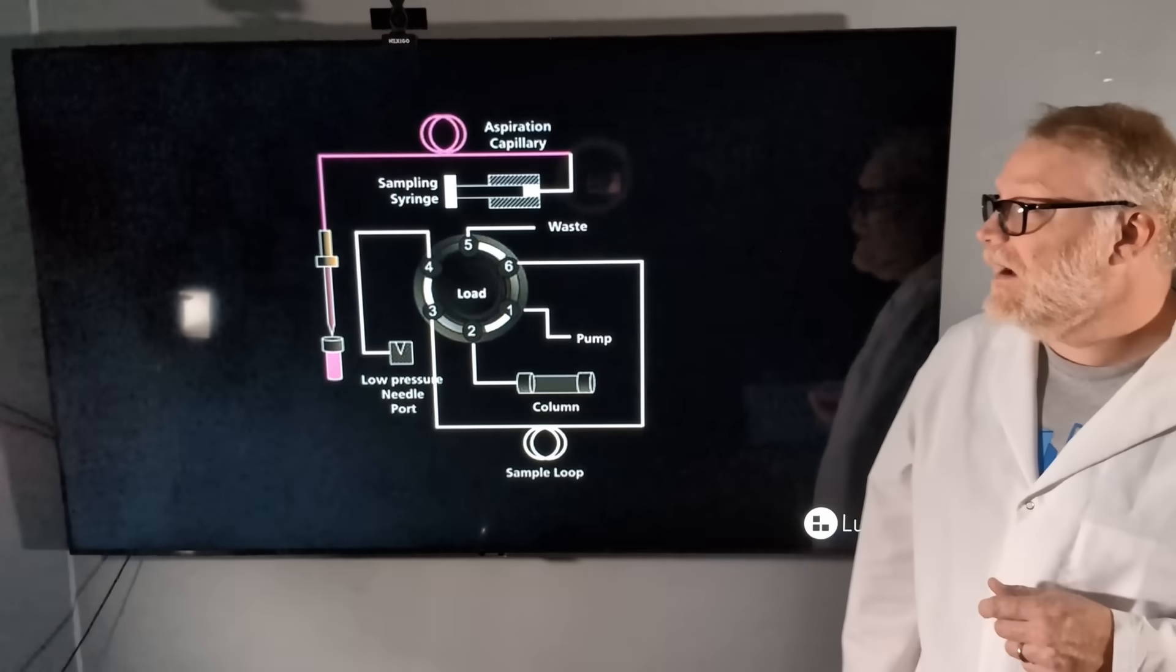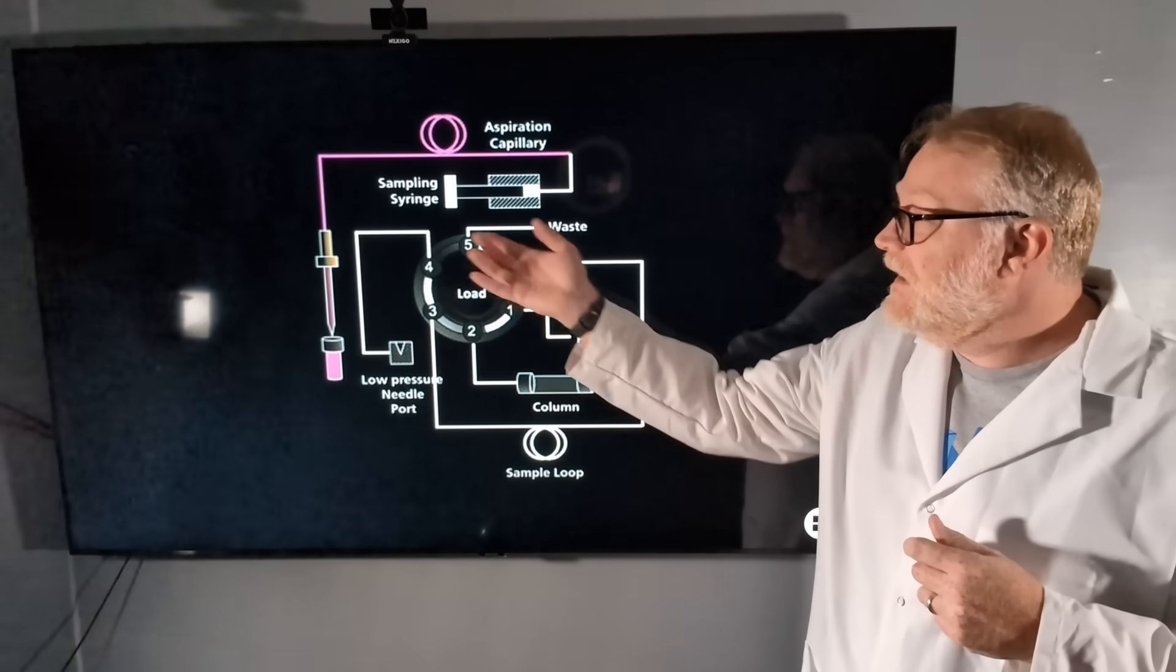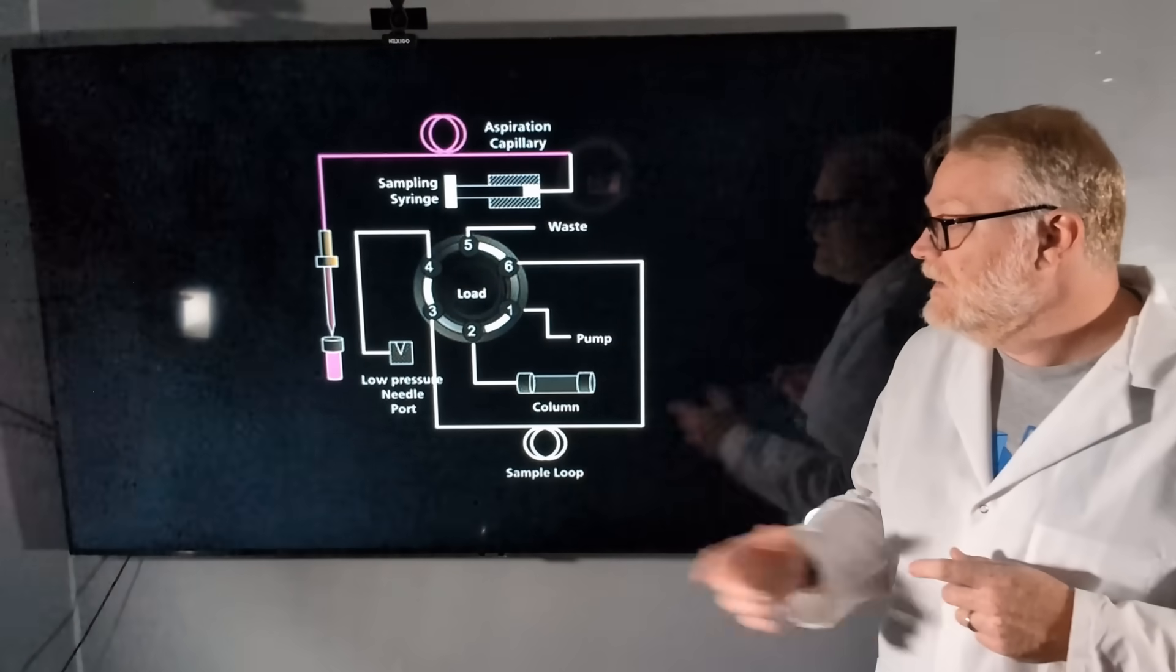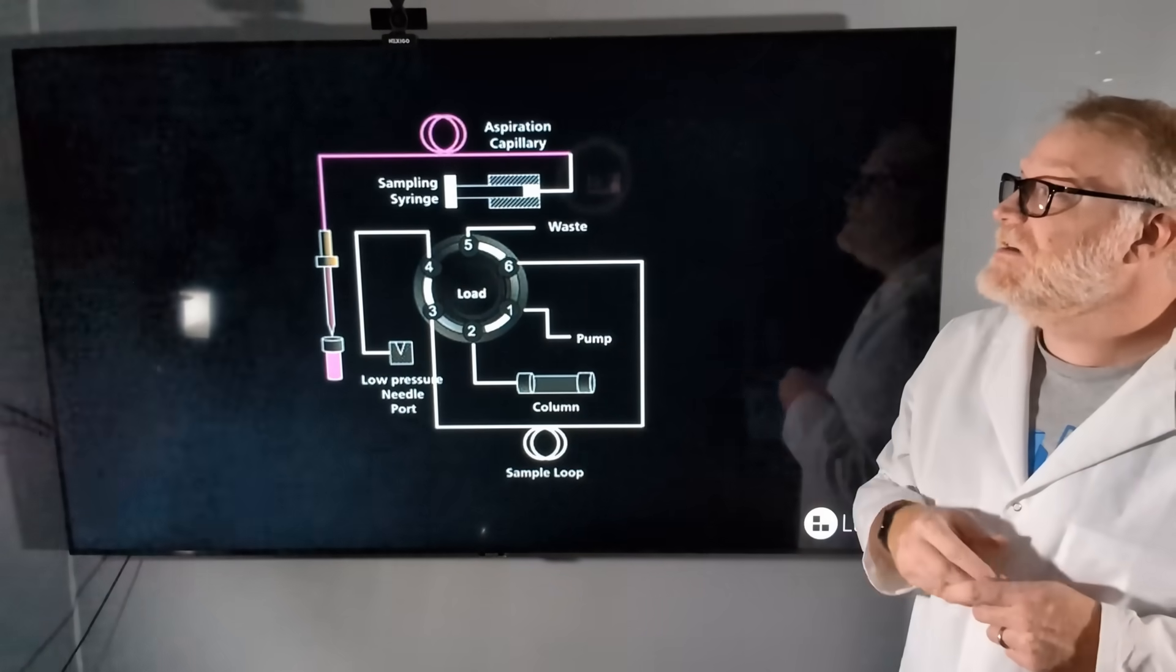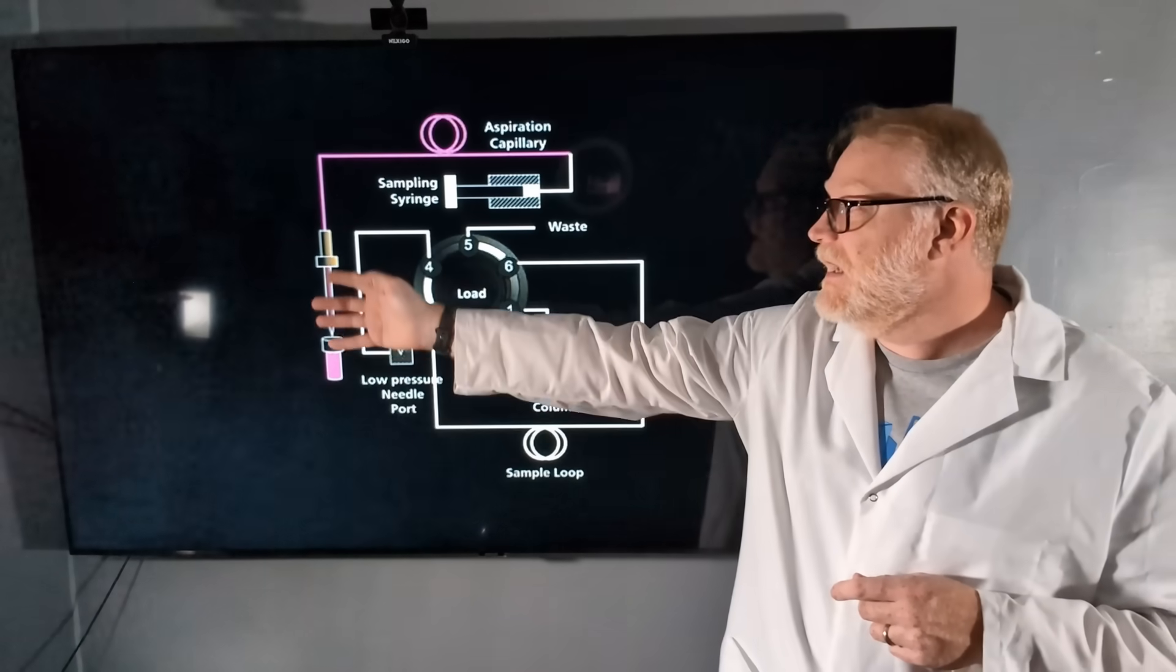An example diagram here shows us our injection valve, our pump and column, our sample loop, our aspiration capillary, sampling syringe, our needle, and a low-pressure needle port.